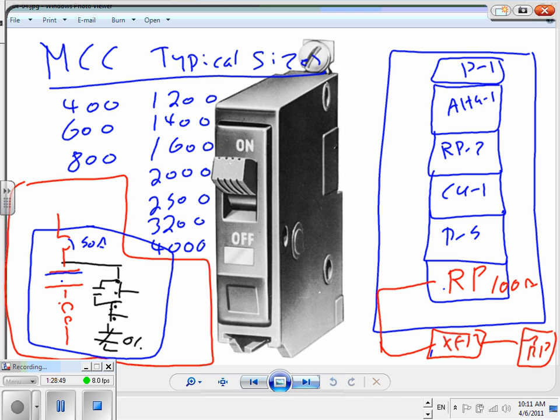Any question, my friends? I want to emphasize, guys, in panels, you can have single pole circuit breaker, 2-pole circuit breaker, 3-pole. 99% of what you guys are going to be installing in commercial industrial is going to be 3-pole circuit breaker, except, anybody can tell me where we use single pole circuit breakers? We could, receptacles and lights.